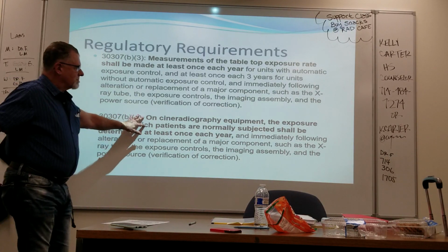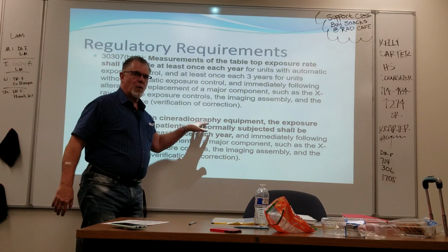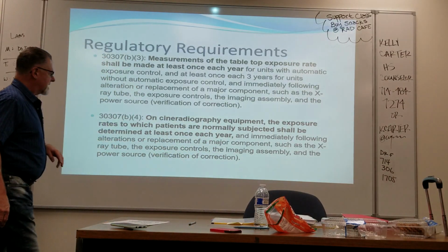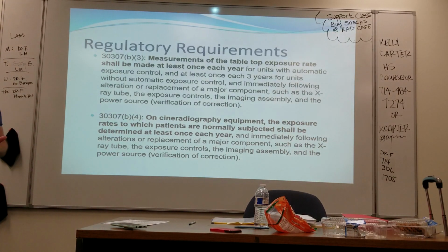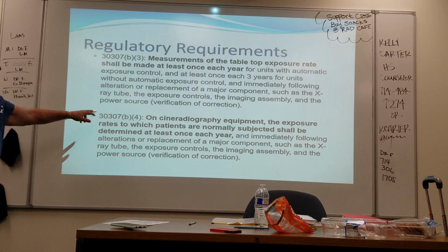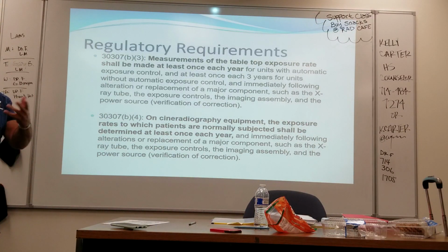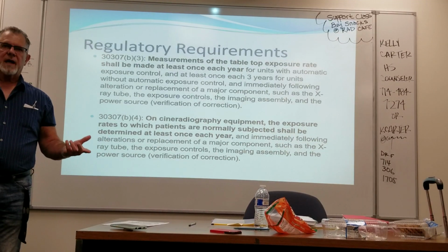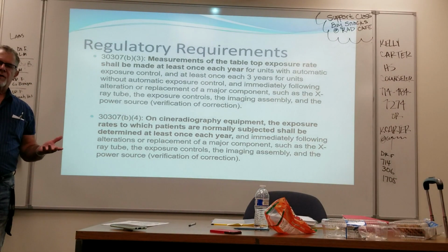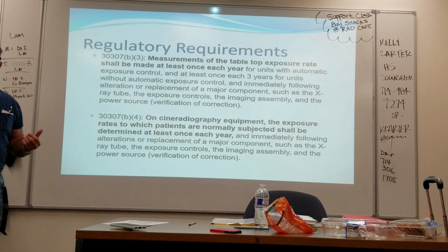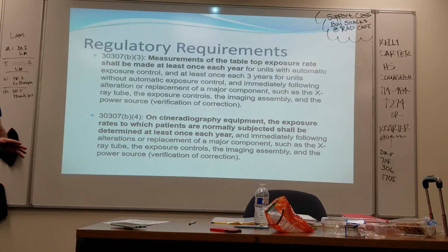Ignore this. Cine radiography equipment doesn't exist, but there is Cine on our digital equipment. State of California has determined that anything over 15 frames per second or more is considered Cine. On older machines, there actually was a button. There was a button and it activated the Cine camera, and it ran 30 or 60 frames per second on 35mm film. That's old technology, it doesn't exist.